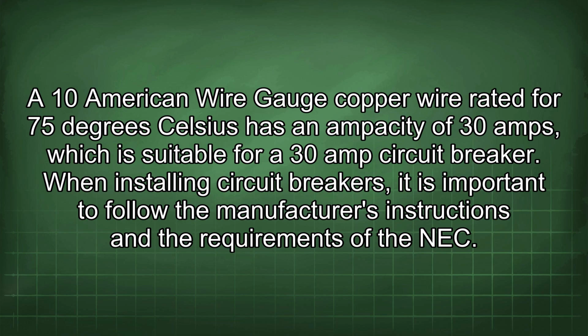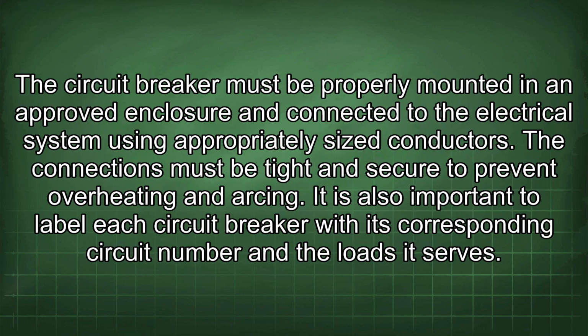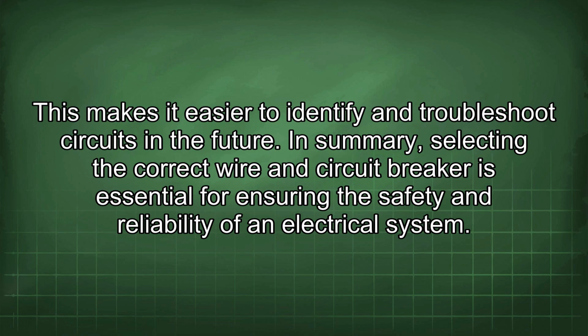When installing circuit breakers, it is important to follow the manufacturer's instructions and the requirements of the NEC. The circuit breaker must be properly mounted in an approved enclosure and connected to the electrical system using appropriately sized conductors. The connections must be tight and secure to prevent overheating and arcing. It is also important to label each circuit breaker with its corresponding circuit number and the loads it serves. This makes it easier to identify and troubleshoot circuits in the future.